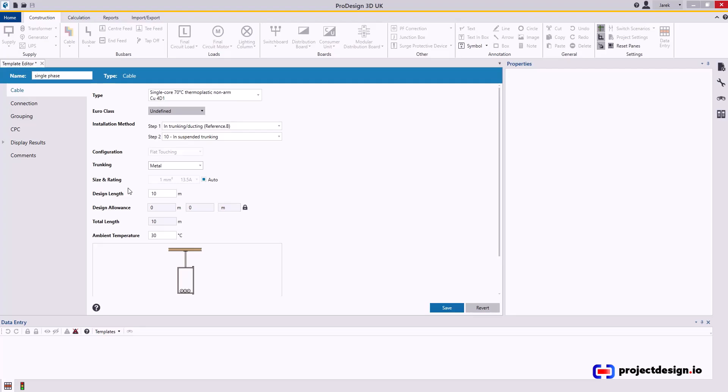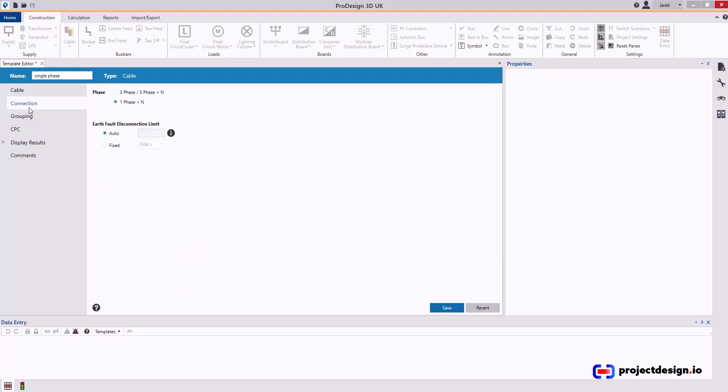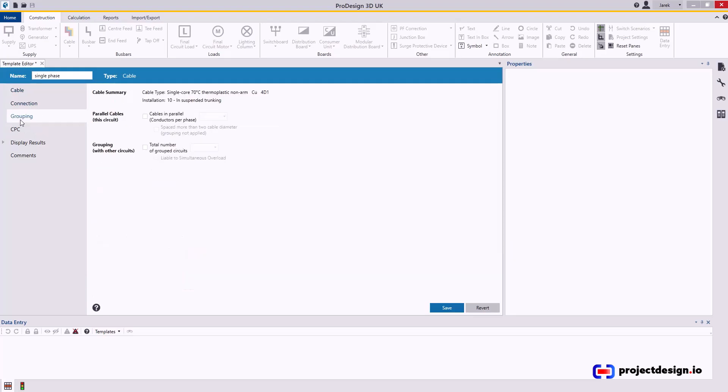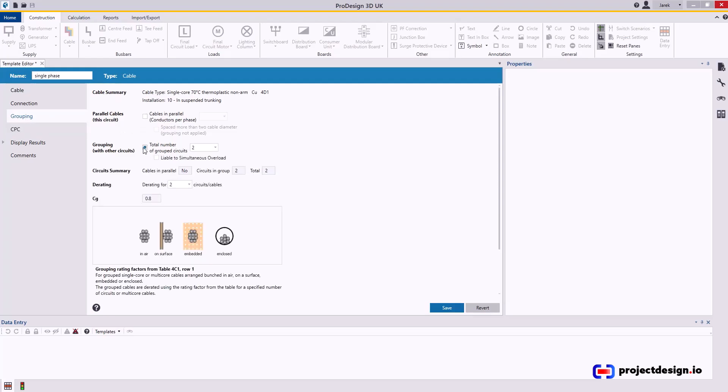I think I need something more like 55 meters as a minimum. Keep everything else the same. Connection, that's single phase grouping. If it's lighting, I would not apply grouping factor. Anything else I will, and there will be no cables in parallel, but you can set up grouping factor to let's say something like five.